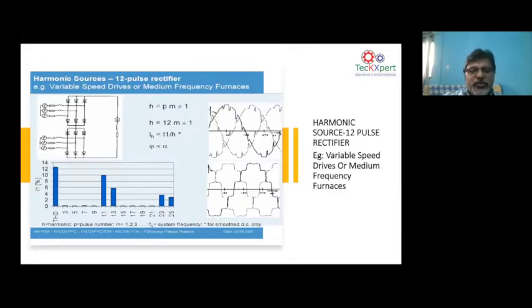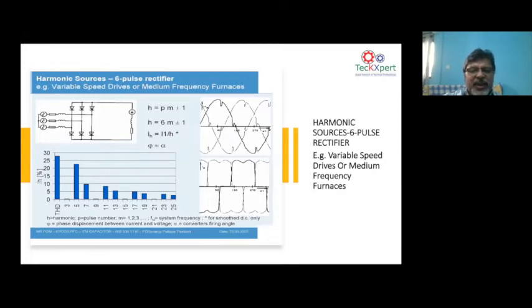Good. And you can also see the current waveforms, as you saw in the previous one. You can see the current waveform, how it looks like. This is how the chopped current will ultimately reflect back on your power line. If you put a harmonic analyzer near the input of the VFD at the incoming side, you will see a current harmonic which looks like the second waveform. The first waveform shows the voltage wave shape. I mean, this is how the voltage looks like. Now, you can see the voltage has a small notch on the top. That means every cycle there's a notch, and the notch is coming from the diode switching.